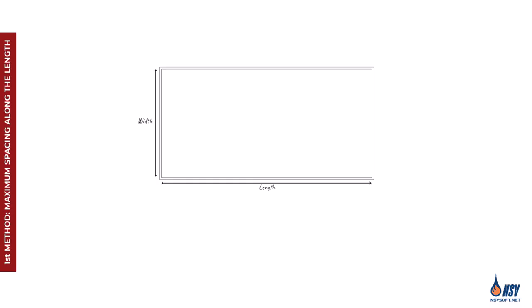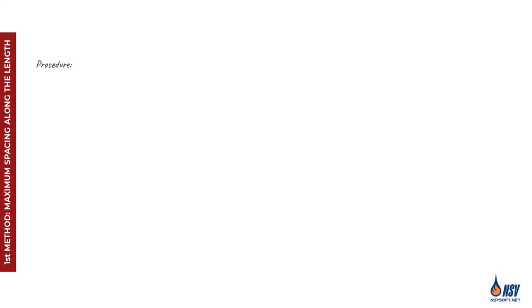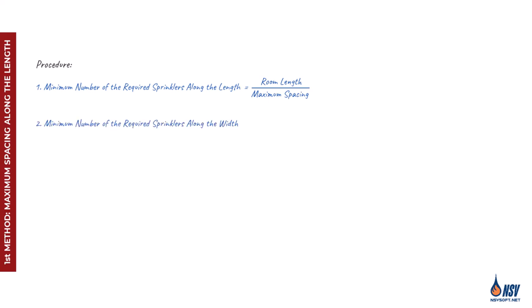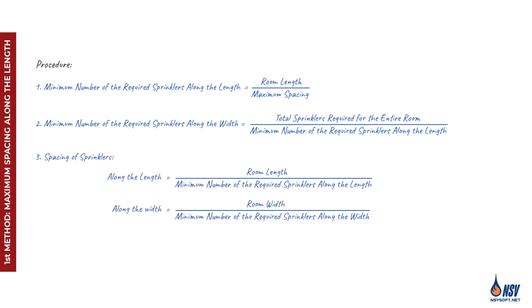The first method for locating sprinklers based on spacing requirements involves placing them according to the maximum allowable spacing along the room's length. This method includes three steps. First, determine the minimum number of sprinklers required to cover the room length by dividing the total length by the maximum spacing permitted by NFPA 13. Second, find the number needed across the width by dividing the total sprinklers required for the entire room by the number positioned along the length. Finally, calculate the exact spacing along both the length and width using the numbers derived from the previous steps.